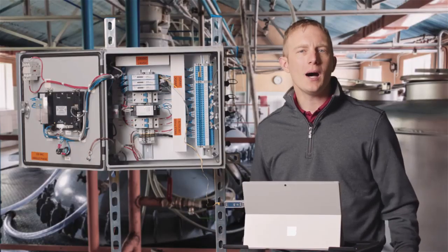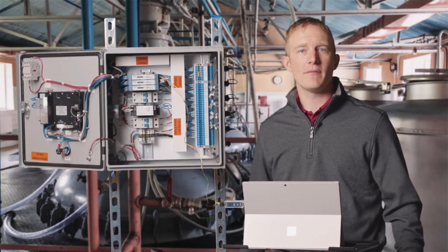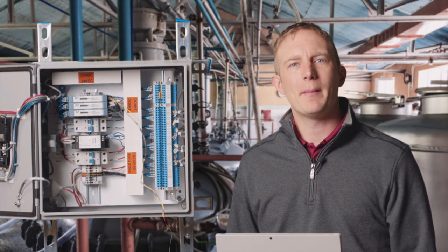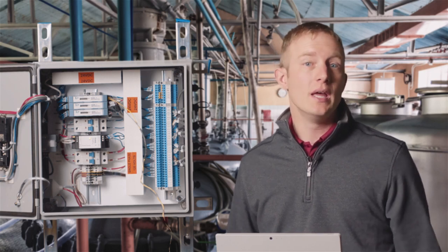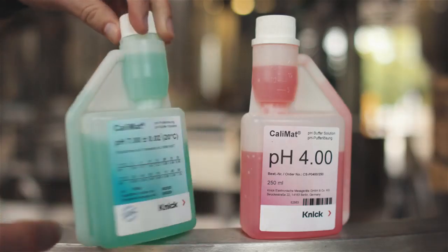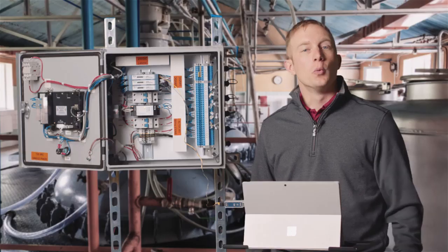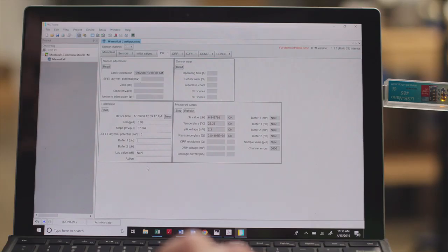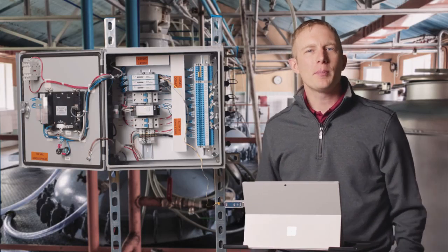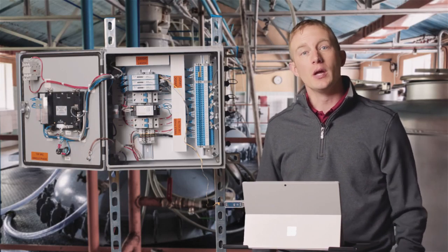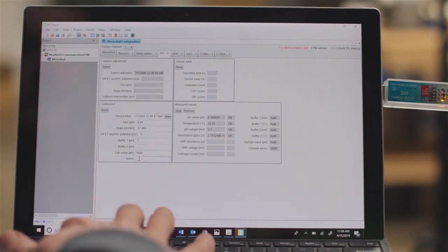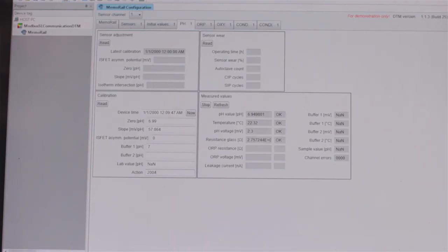Please note that we want to compensate for the temperature value of our buffer solution. This should be done by monitoring the measured temperature value and cross-checking it with the table provided with your buffer solution. We'll now enter the temperature compensated value of the first buffer solution in register 2528 and hit enter to continue. Once we have entered the proper value of our first buffer solution, we will write the value by using action code 2004 in register 800 and pressing enter.